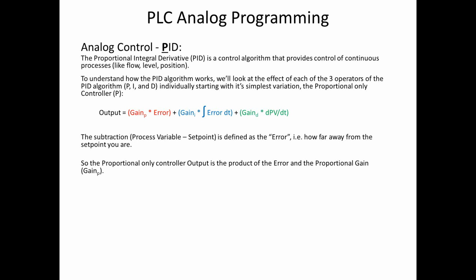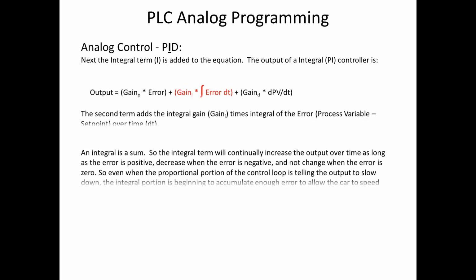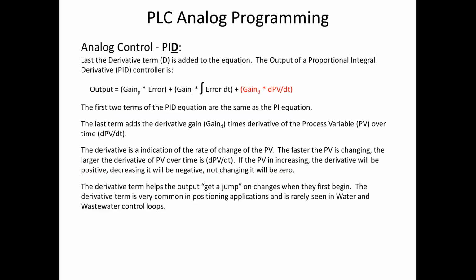The integral accumulates the error between the two so that it can help you fine-tune the proportional control. The derivative concerns itself with the amount of change per time unit, so that if you see something changing very rapidly, you may need to enact some type of control to help dampen that out. I'm going to blast right through this to tell you that the derivative term gives you a jump on the changes when they begin. The derivative is very common in positioning applications. However, you don't see it very often in water or wastewater.